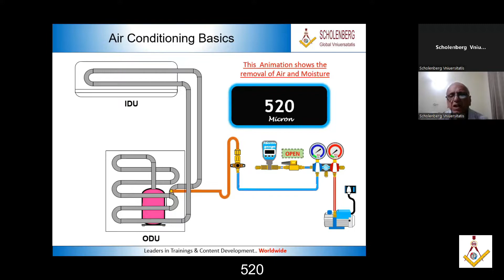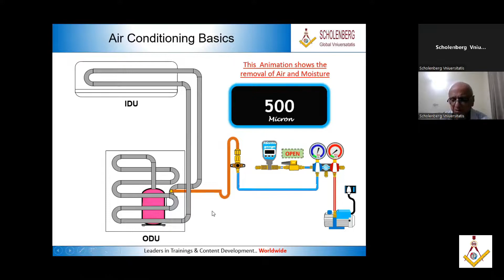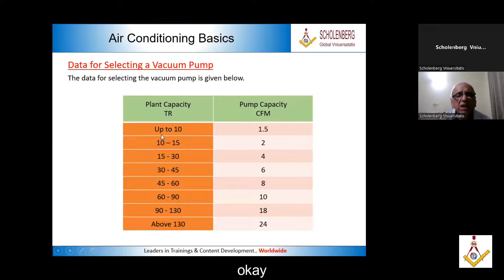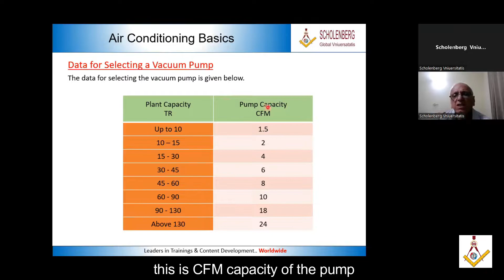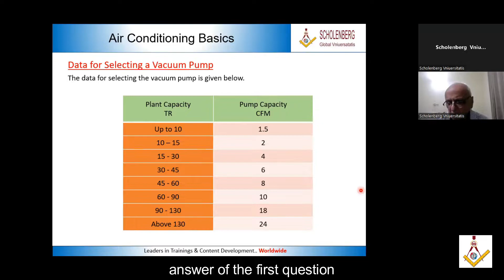This is the setup of the system. The vacuum pump, this is a manifold. You have a ball valve, the micron gauge, and this is how it is connected to the system. So this is what I was talking about. So this is the plant capacity in TR, and this is the CFM capacity of the pump. That was the answer to the first question.